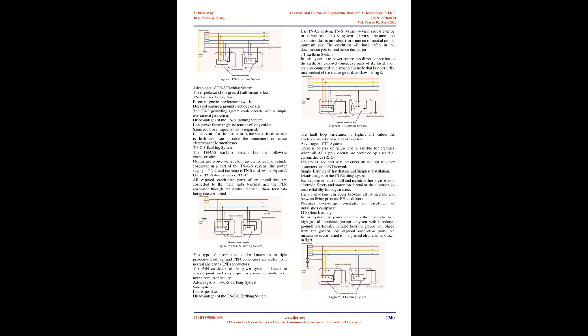Defects in LV and MV networks do not go to other customers on the BT network. Simple earthing of installation and simplest installation. Disadvantages of the TT earthing system: each customer must install and maintain their own ground electrode. Safety and protection depend on the customer, so total reliability is not guaranteed. High overvoltage can occur between all living parts and between living parts and PE conductors. Potential overvoltage constraint on insulation of installation equipment.